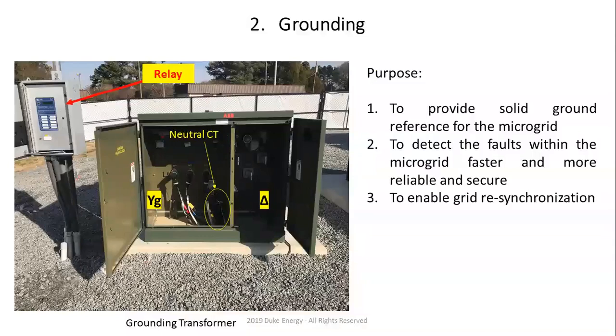But if you have battery plus PV, or battery plus PV plus generator, at any point in time where battery plus PV are the only resources within the microgrid, you must add this, right? So the grounding transformer is disconnected when it's connected to the grid, for the same reason that I showed you before, because it would have an effect on the line-to-ground faults regarding whether you have a DR or not. And it's connected to the island when we go into island mode, right?